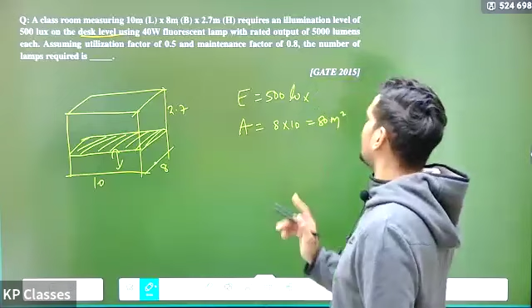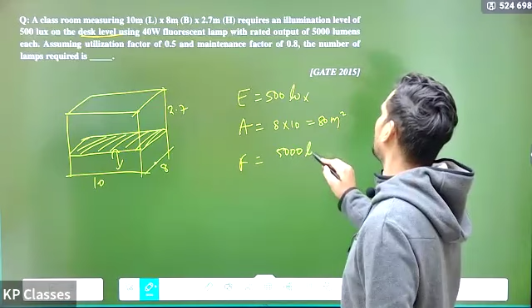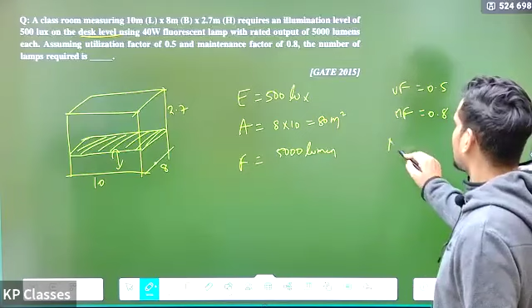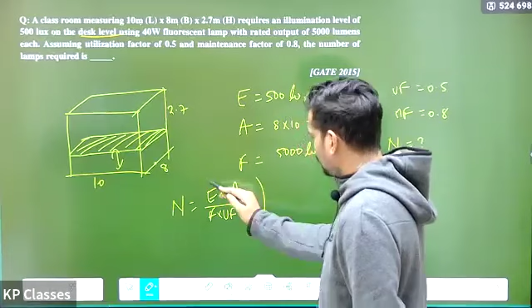They are using a 40-watt fluorescent lamp, and the flux output of each lamp is given as 5000 lumen. And utilization factor is given as 0.5, maintenance factor is given as 0.8. If the factors are not given, you will directly take them to be 1. If the factors are given, you will consider the value given. They're asking us the number of lamps required. I told you, number of lamps is illuminance multiplied by area divided by flux into utilization factor into maintenance factor. So how much is this? Illuminance is 500 lux, area is 80 square meter, flux output of each lamp is 5000 into utilization factor 0.5, maintenance factor 0.8.